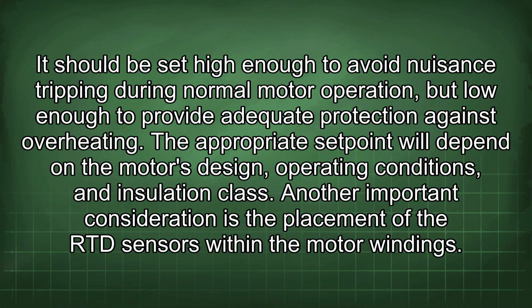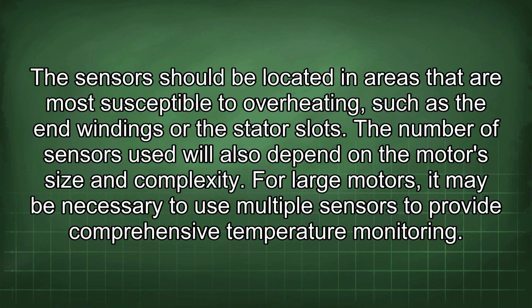Another important consideration is the placement of the RTD sensors within the motor windings. The sensors should be located in areas that are most susceptible to overheating, such as the end windings or the stator slots. The number of sensors used will also depend on the motor's size and complexity. For large motors, it may be necessary to use multiple sensors to provide comprehensive temperature monitoring.